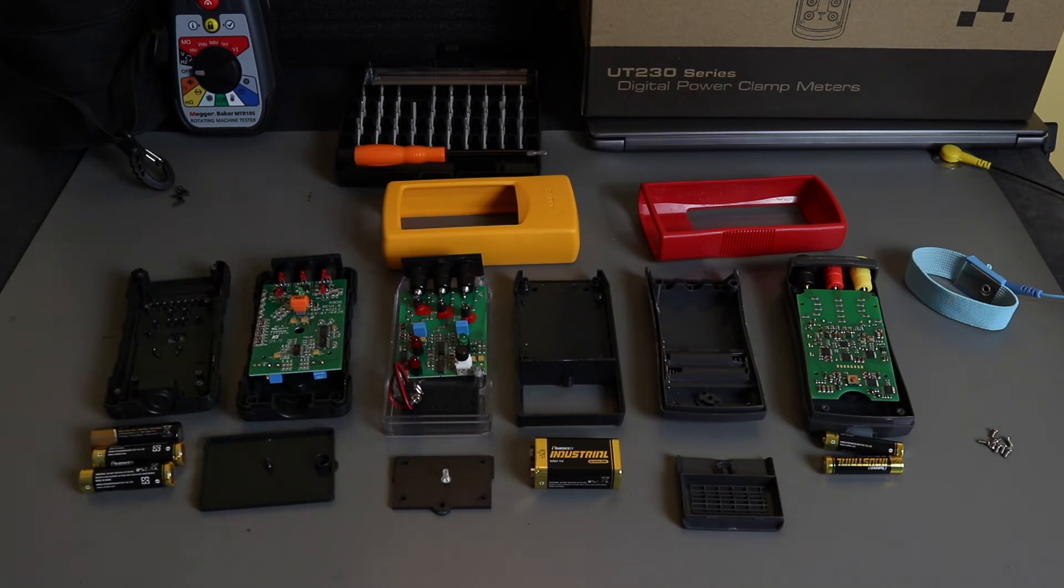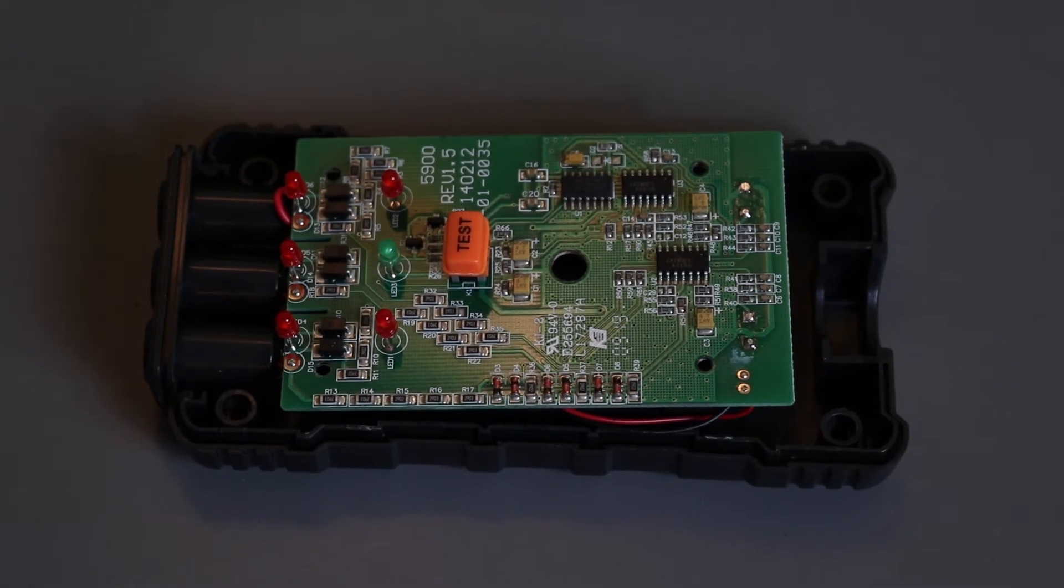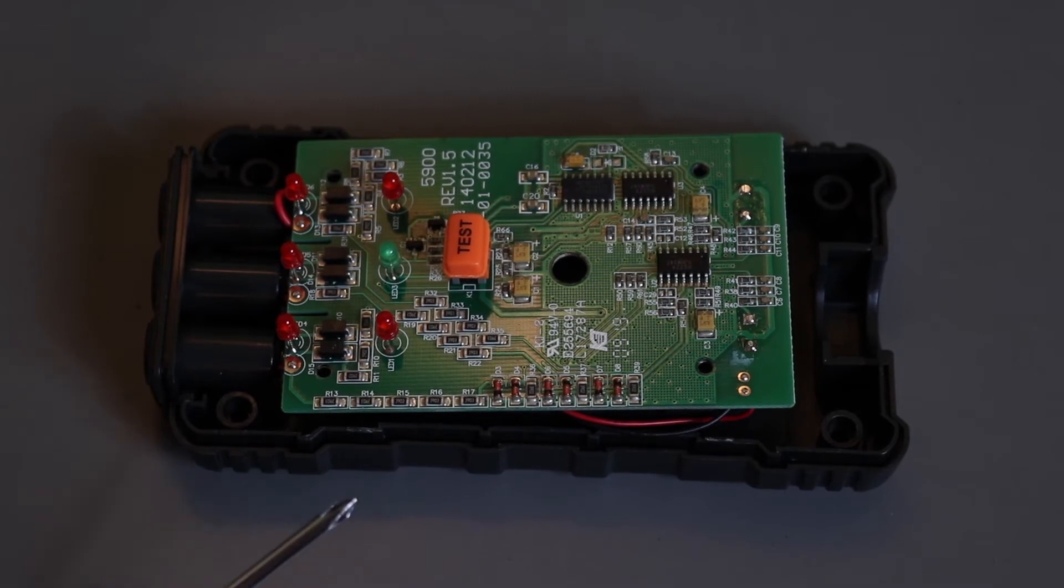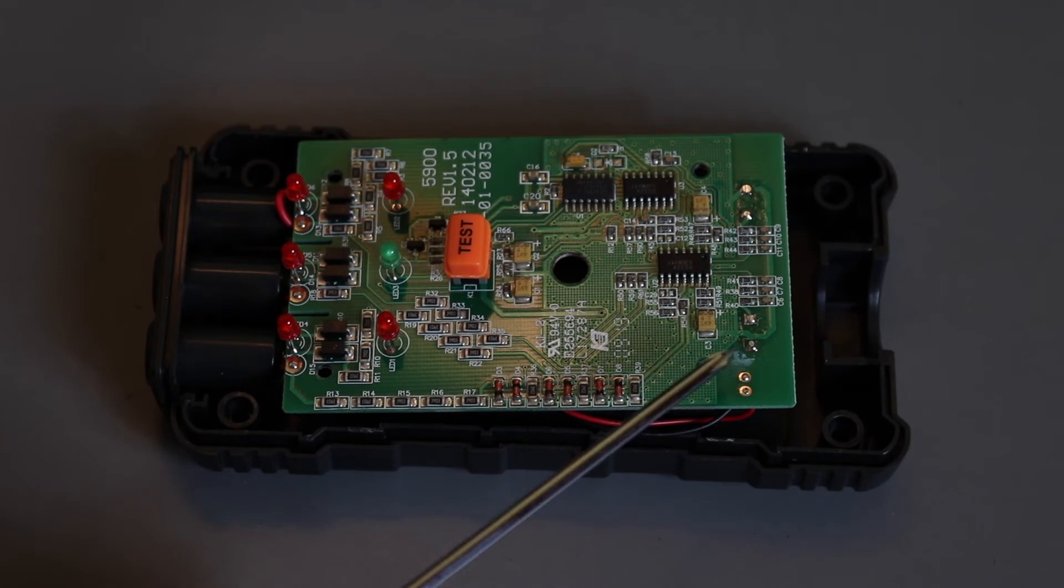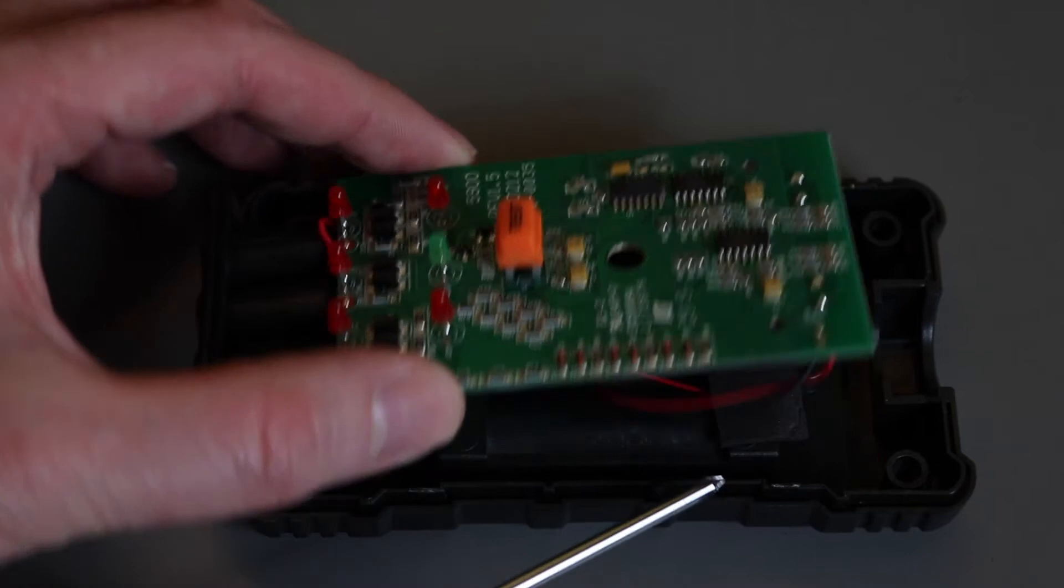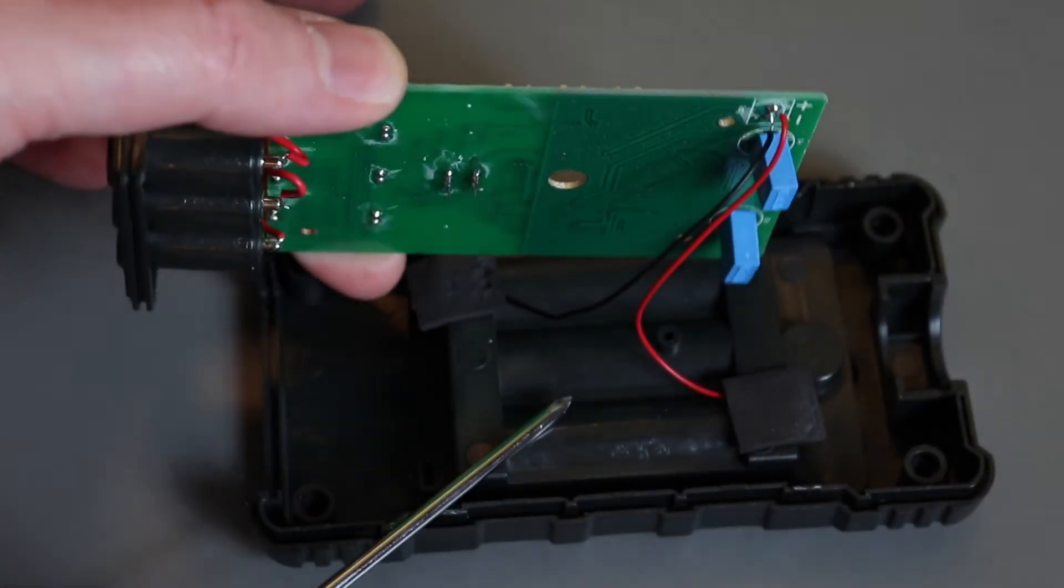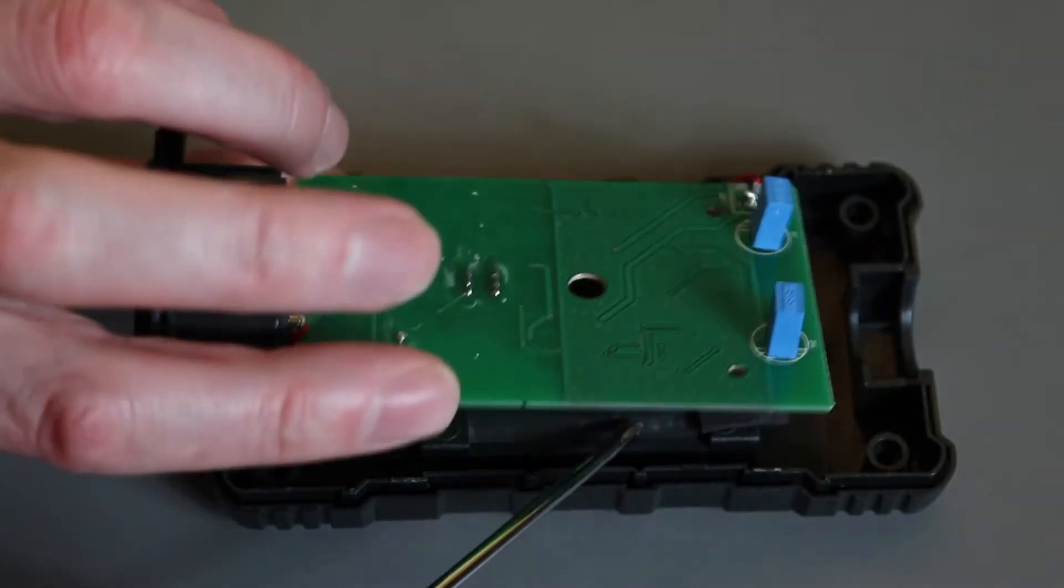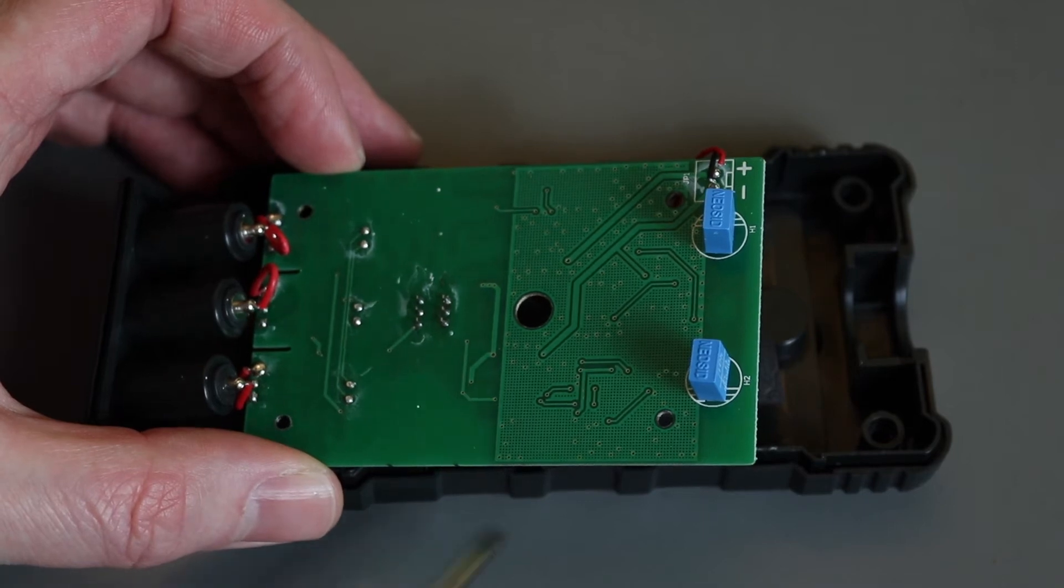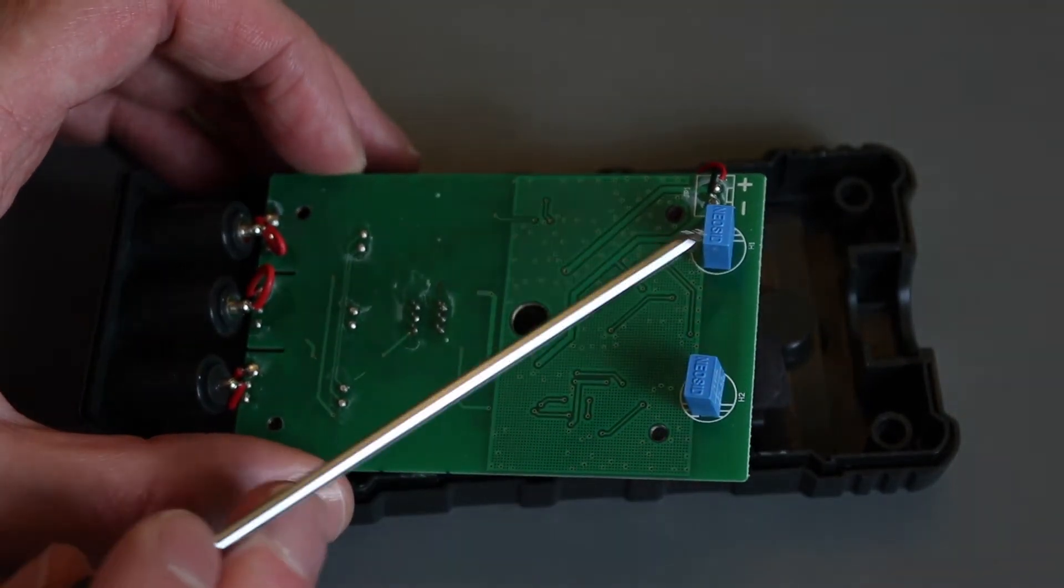This is the close-up view of the Peak meter unit. As you can see here, the PCB is pretty clean, no real major problems on this side. There's a bit of solder residue over here. The board is actually hardwired onto the battery pack here, so not so easy to remove. On this side is a bit more solder residue here, and you can see these two are the inductors for the magnetic pickup of the phase rotation when held against a motor.